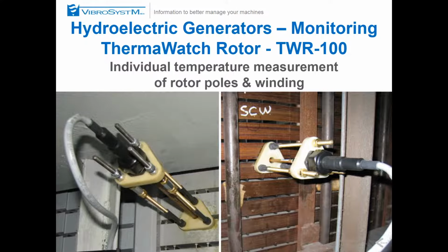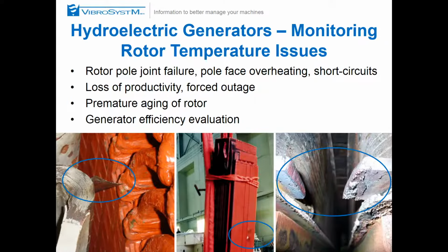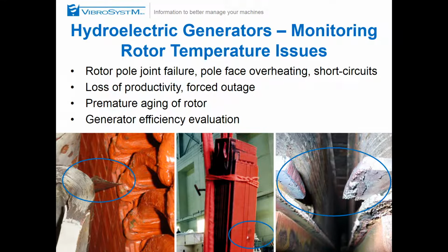Okay, so more pictures here of the bracket with the probe inside. And also what you can do is look at pole joints. Pole joints, especially the flexible ones, as you can see on the right here. The flexible ones, of course, if the unit is cycled a lot, so the unit will expand, contract, expand, contract, and these are susceptible to cracks and eventually fail. And you can see the entire pole joint was vaporized. In some cases the flexible ones are much better, but as you can see, they're still susceptible to some damage. You can see one lamination has actually come off, and eventually this can fail.